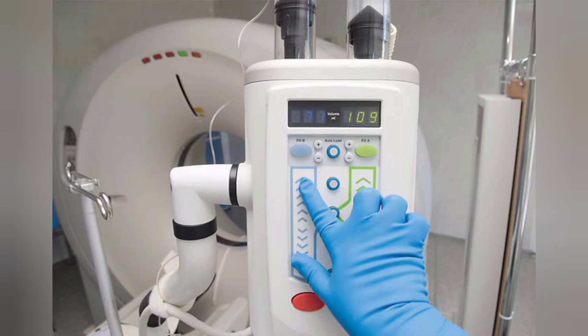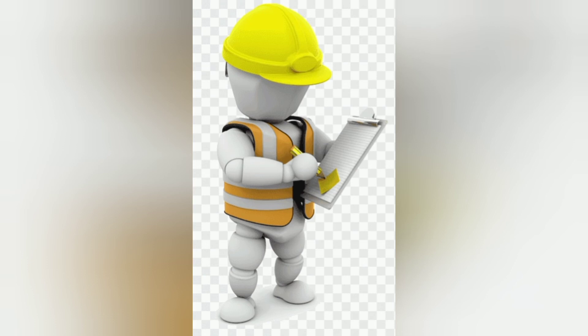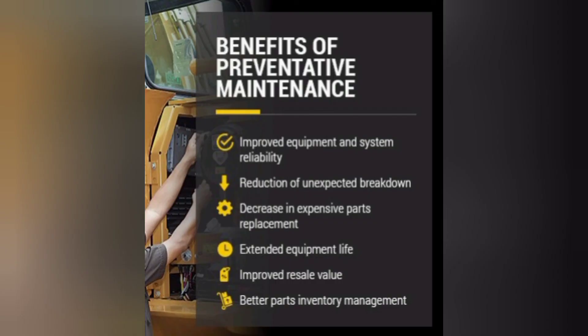After closing, do the functional testing of the machine. Make a report of the maintenance. In the report, include your key observations about the equipment and do not forget to note any suggestions for the user if needed. After writing everything in the report, take the signature of the sister in-charge or any other accountable person of that department. Now the preventive maintenance procedure is complete — store this report in your record file.